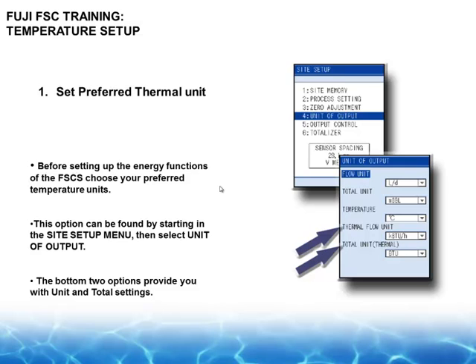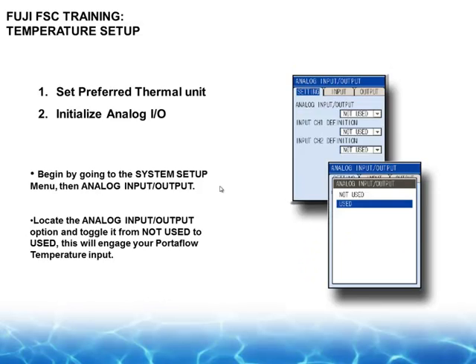And the way that you set this up, so this is in the advanced level if you're monitoring BTU, we need to go and set up the energy functions on the Portaflow-C. This option can be found by starting in the Site Setup menu, and then select Unit of Output. And the bottom two options provide you with the unit and total settings.